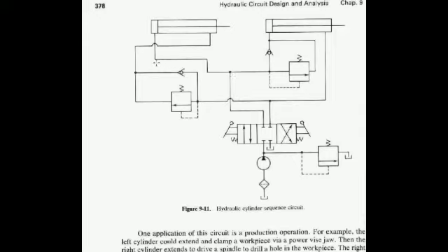The only option is it has to flow to the blind end of the first cylinder, so that I will get the extended motion, right? So while getting the extended motion, the rod end side of the cylinder will flow in this manner, and we are having again two options here, either via the check valve or via this sequence valve, but we are not having an option for the flow via this sequence valve. It has to flow through this check valve only, and that can be fed to this line and to the port B, from B to the T, right?